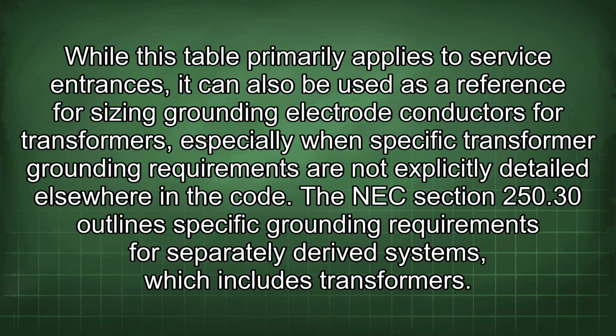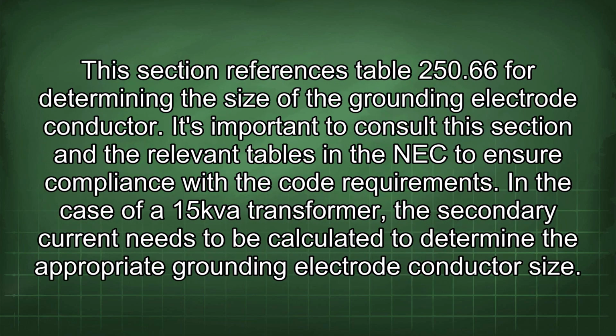The NEC Section 250.30 outlines specific grounding requirements for separately derived systems, which includes transformers. This section references Table 250.66 for determining the size of the grounding electrode conductor. It's important to consult this section and the relevant tables in the NEC to ensure compliance with the code requirements.